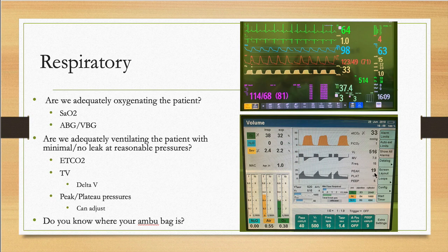And of course, while you're looking at the tidal volumes, you can look at peak and plateau pressures. It was previously told to me that the machine itself doesn't actually have plateau pressures because technically there's no inspiratory pause. However, in the machine settings, in this little extra settings button, you can actually find an option where you can add an inspiratory pause of a certain percentage to help you tease out a plateau pressure.